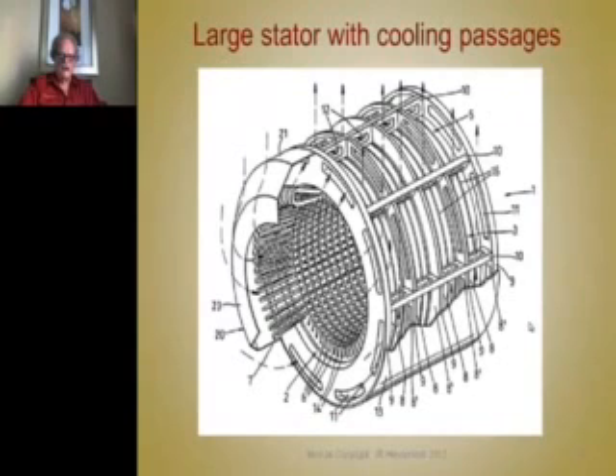Now here's a very large stator, a huge stator that's not nearly as compact as that one. As you can see, the laminations of the stator are stacked in packets with vent plates between them. We saw those on the last slide, or on the last workshop. And so the conductors for the phase windings go down these open slots, and they're in this chamber here, and they pass through these vent places, so there's direct contact. If you can get air or gas to go through those ventilation places, then you're getting direct cooling right on the conductors that pass through there.